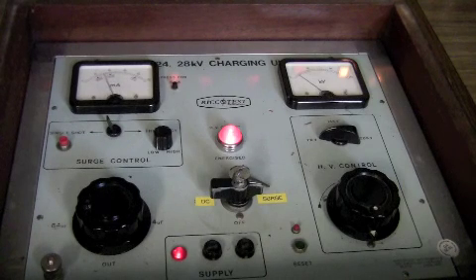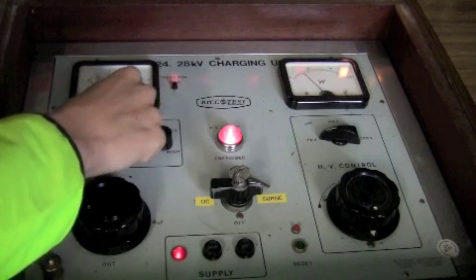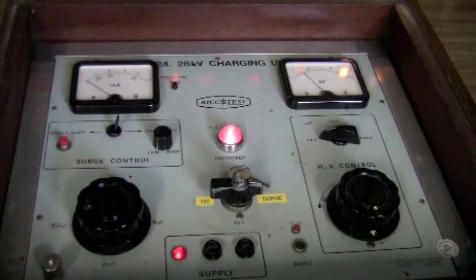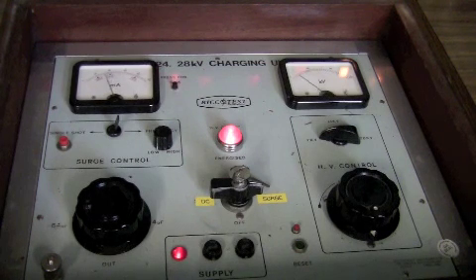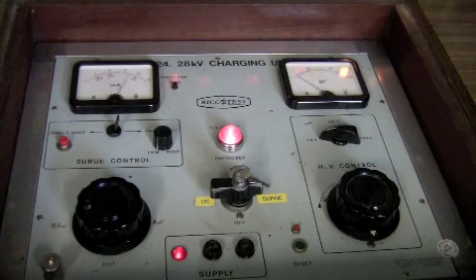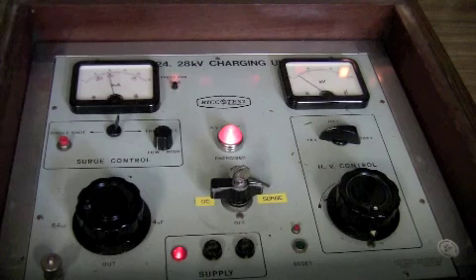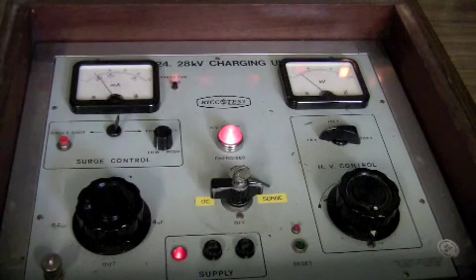Now so that I can go and listen to the fault with the sensitive listening equipment, I can switch this over to frequency and the test set will now pulse into the cable at regular intervals somewhere between six and seven seconds, creating an acoustic noise where the fault position is.